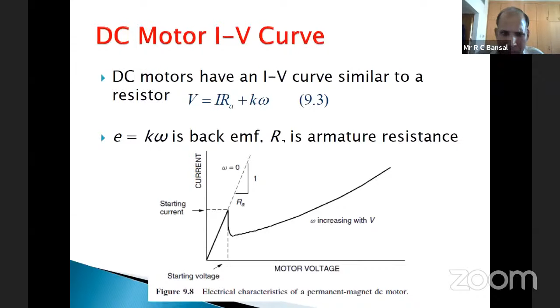So here you saw that we superimpose the DC motor characteristics on the IV characteristics of the PV systems. Depending upon sunshine during the day, the current keeps on changing. The motor will require this much current during starting, but if we have some device which can help in starting the motor, it can be started corresponding to say 200 watt per meter square, early in the morning. Once the motor started, it keeps on running for extended hours, so it can supply water for a significant number of hours. So the performance of the water pumping systems can be enhanced.